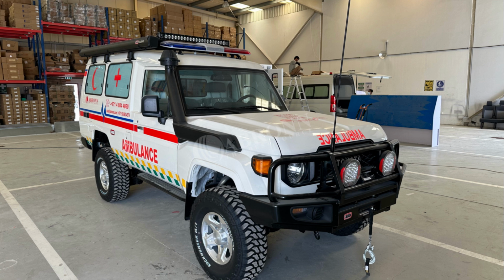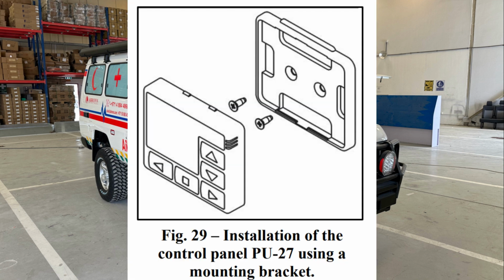Never extend the cable of the control panel itself, as it is transmitting a digital signal. In the event of a bad connection, this will result in malfunctions. Use designated control panel wiring extensions.